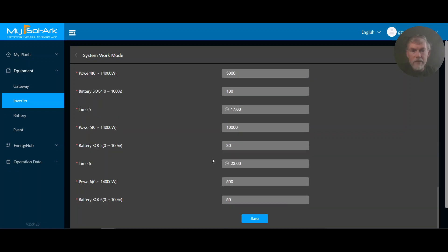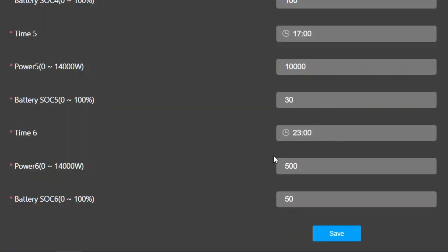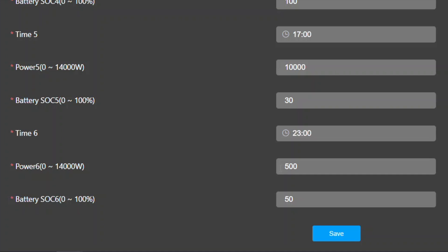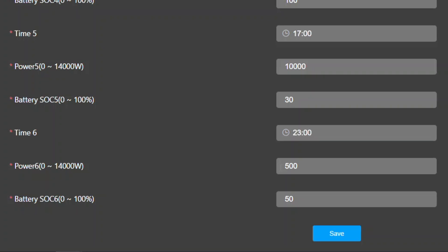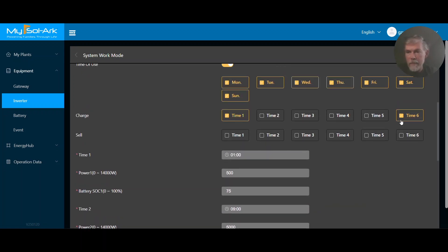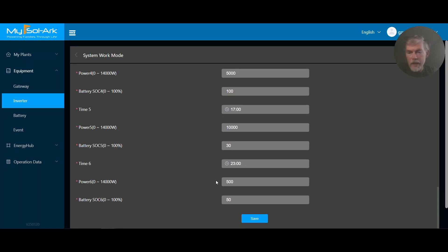At time zone six, starting at 11 p.m., it can discharge at 500 watts up to 50% SOC. Since the battery is already below 50%, the only way it could reach 50% is by charging. There's no sunlight at that time, so in the current setup it just sits at 30%. But now that I have 'charge' checked for time slot six, it's going to charge from the grid up to 50%, giving a little boost to the batteries. This isn't really needed in summertime, but it's very helpful in wintertime. You may want to come in and adjust these settings every once in a while to improve system performance.